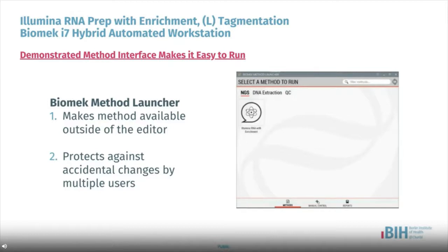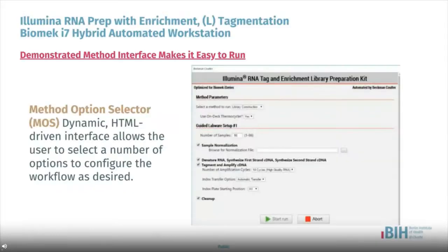The Illumina RNA Prep with Enrichment demonstrated method is designed to run with Biomek Method Launcher, a user interface that allows users to run Biomek methods outside of the Biomek 5 Method Editor software. This protects against unintended or accidental changes by multiple users while preparing to run methods. Run parameters are defined using the method options selector, a dynamic HTML-driven interface that allows users to select parameters such as number of samples, use of the automated thermocycler, which indexes to use, and method start and stop points. Parameters that would create an error state will display an error and not allow the user to proceed.